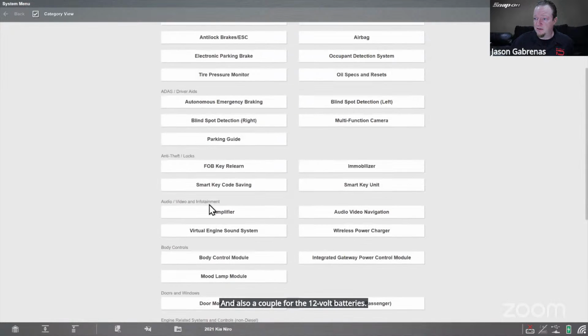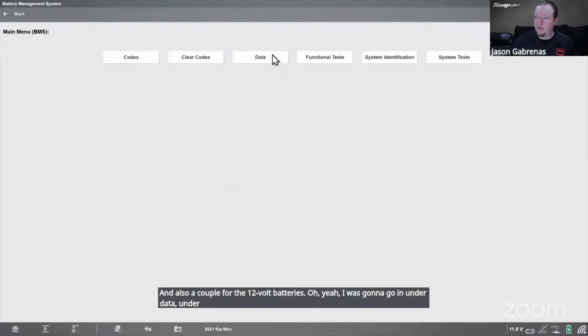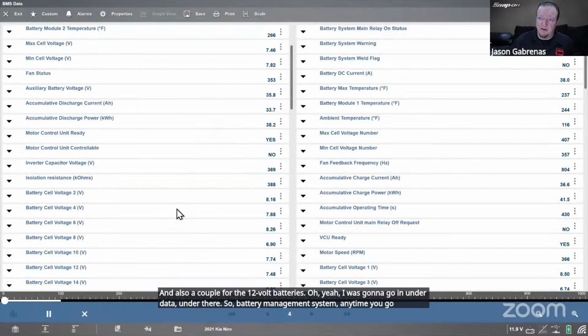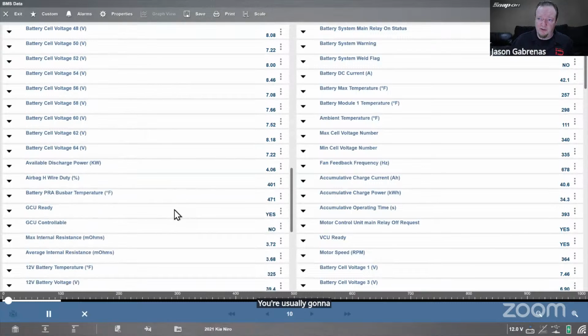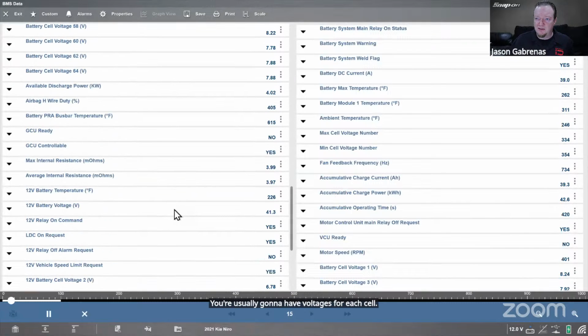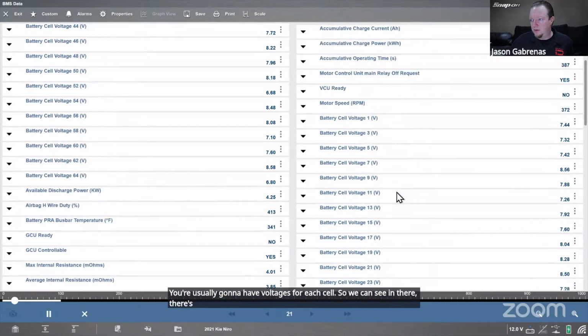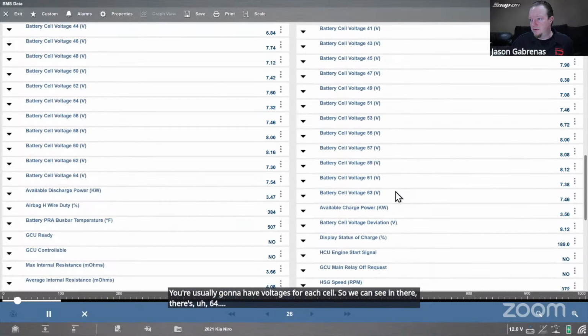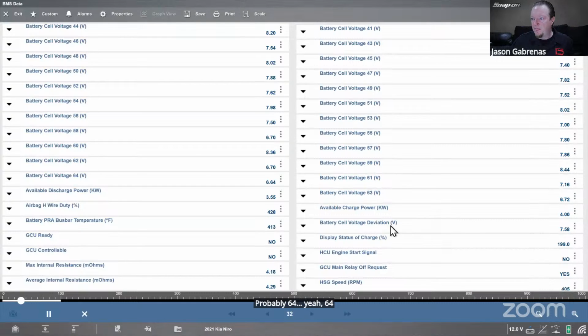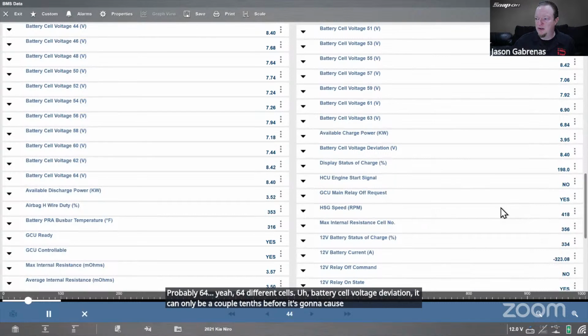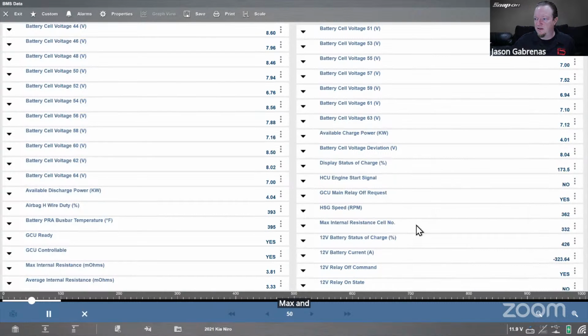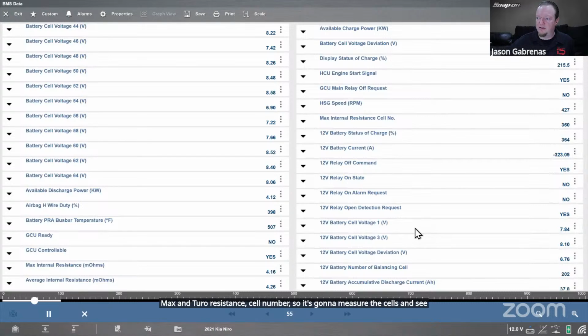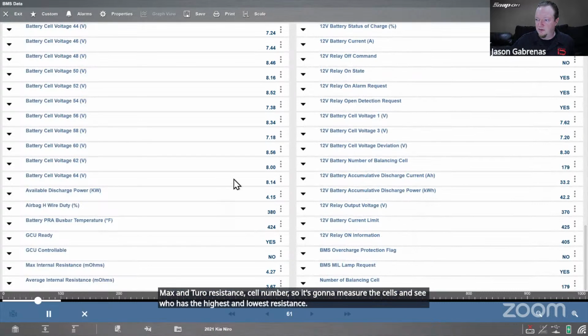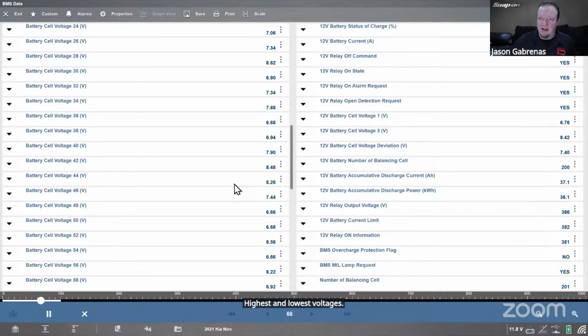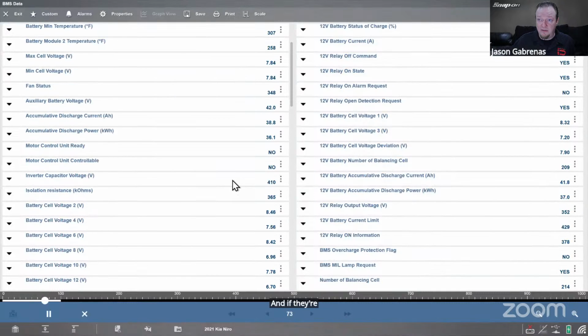I was going to go into data under there. So battery management system, anytime you go into it you're usually going to have voltages for each cell. We can see there's 64 different cells. Battery cell voltage deviation can only be a couple tenths before it causes problems. Max internal resistance, cell number, so it measures the cells to see who has the highest and lowest resistance, and highest and lowest voltages, because they want to be balanced. If they're not balanced, then you have an issue within.